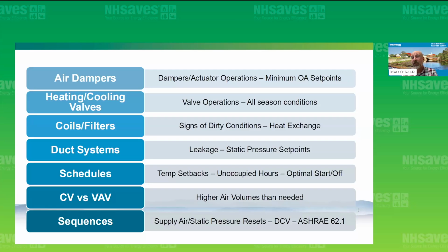And if it can't be easily retrofit, just identify it as, next time you're changing this out, don't do a like for like change. This one can be changed with a more efficient VAV system. And then sequences. Sequences that were put in to save energy are where modifications commonly happen over the years and need to be reviewed for optimal performance. So they can also be modified to find savings with small changes.